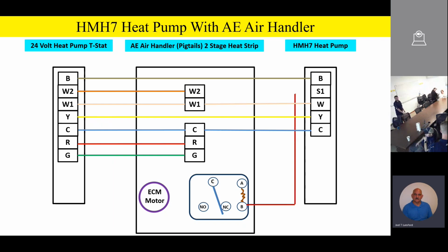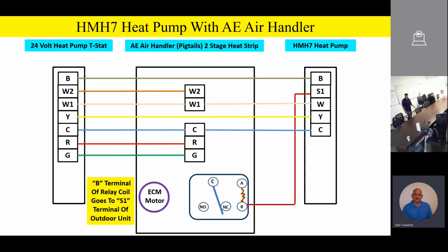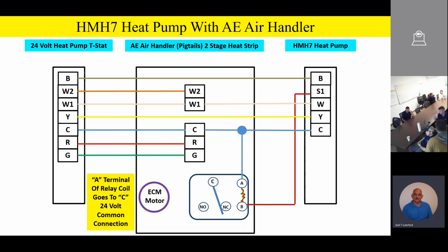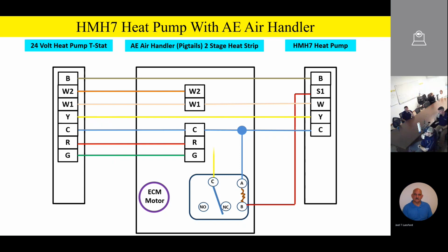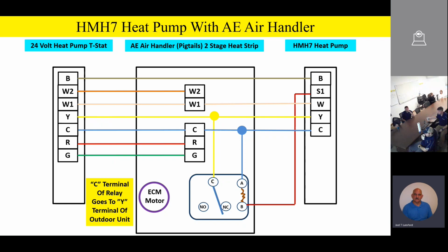Now, a couple things. We had mentioned that we've got that relay, that 001 relay. So when we hook up the relay, we need to remember that one side of the relay coil itself will be going to S1, which is the output from the outdoor unit to bring that relay on for airflow reduction. So this is going to be important that we understand how this airflow reduction works. The other side of the coil is going to go to 24 volt common so that we can operate the relay coil when necessary. We're also going to see that the common terminal for the switching contacts is going to go to Y. So anytime we have a Y call for compressor operation, we're going to be feeding power to the switching contacts on the relay.